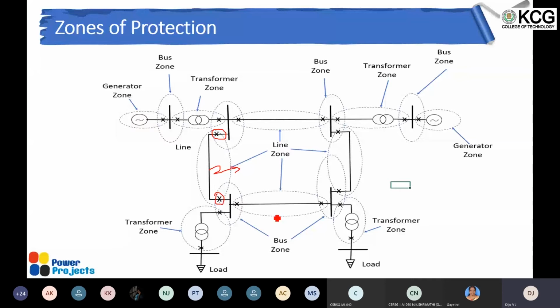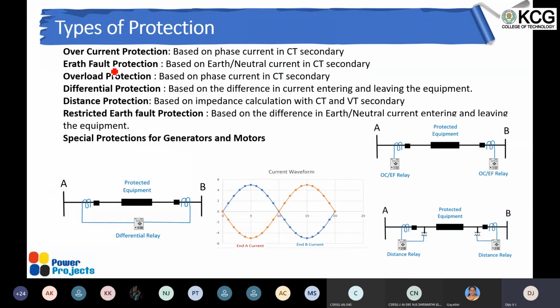All of you might know that the different types of protection include overcurrent protection. That's a very basic protection principle. When the current through the feeder is higher than some set value, the relay operates. There is a relay kept here, and when there is a fault somewhere here, the relay senses the current through it, which comes out of the CT secondary, because you cannot feed the current measurement to the relay directly from the primary circuit. So we need to go for the CTs, and the CT secondary current will always be proportional to the primary current.